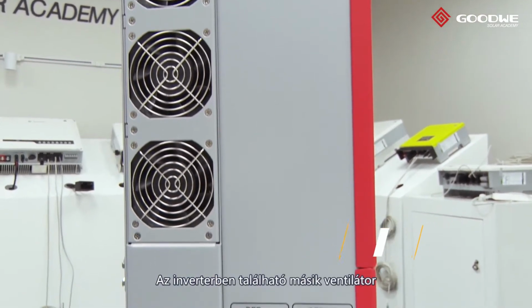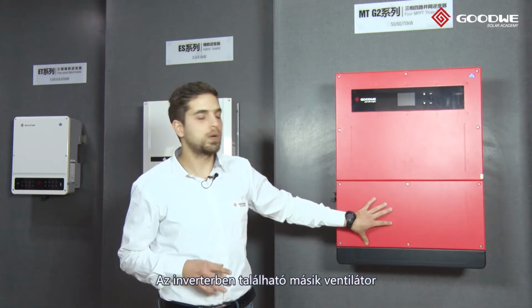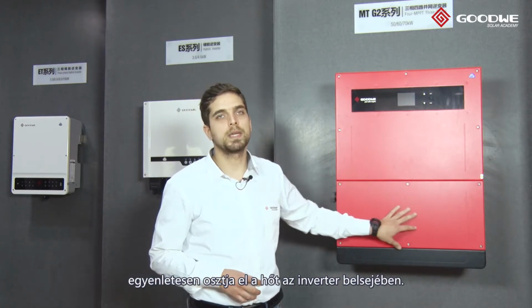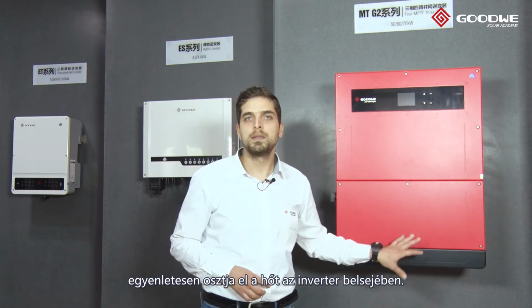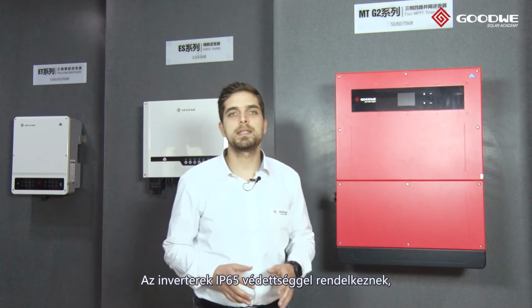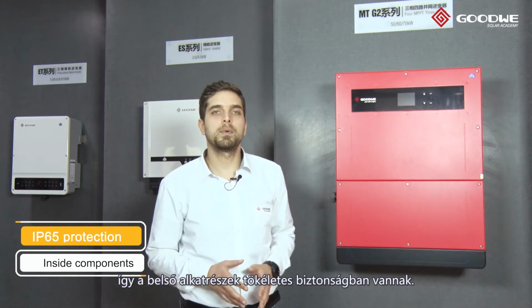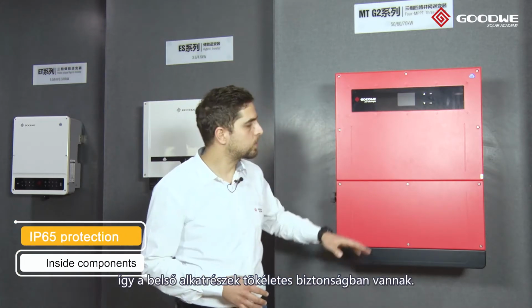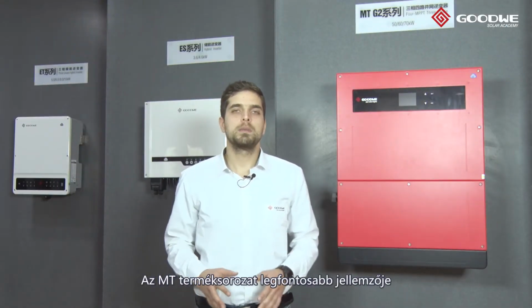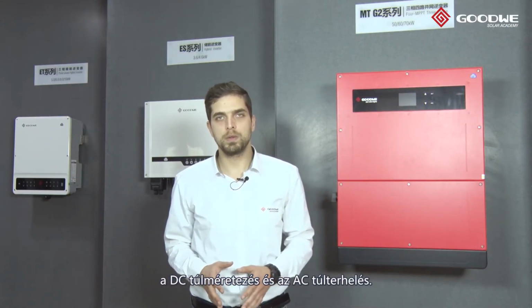Also, one other fan is located inside of the inverter to make sure all the heat is distributed equally inside of the inverter. This inverter comes with IP65 protection, so you don't have to worry about the protection of the inside components. One of the most important features for MT series is high DC oversize and AC overload ability.